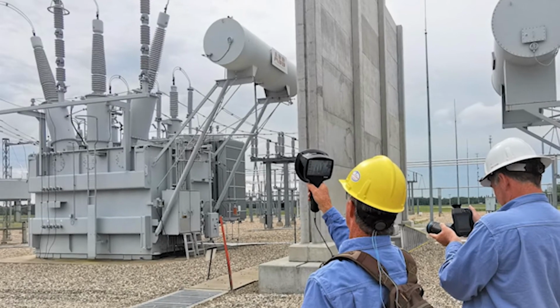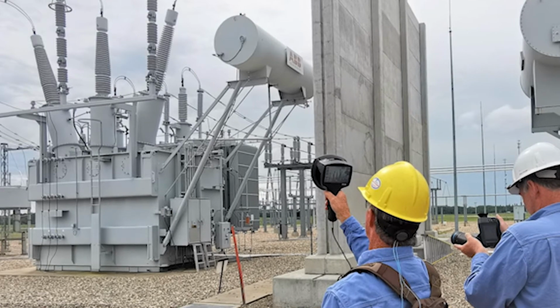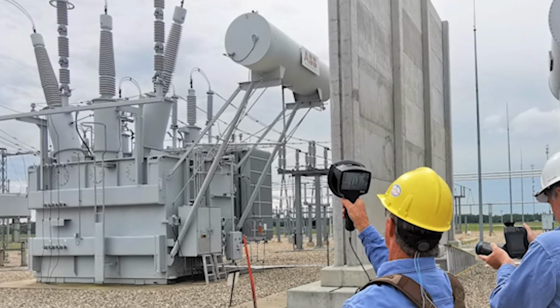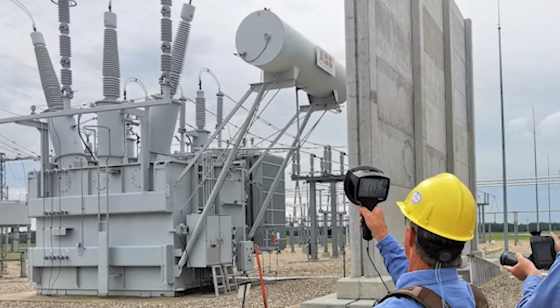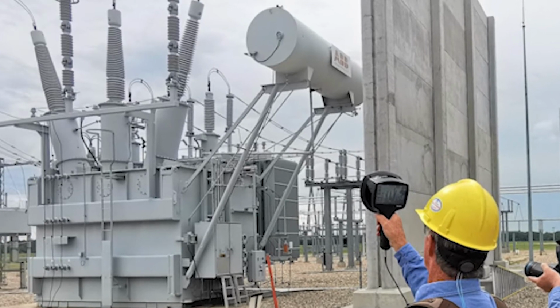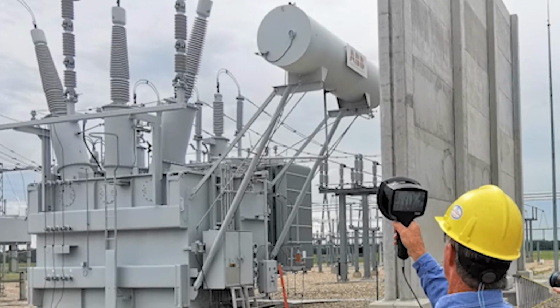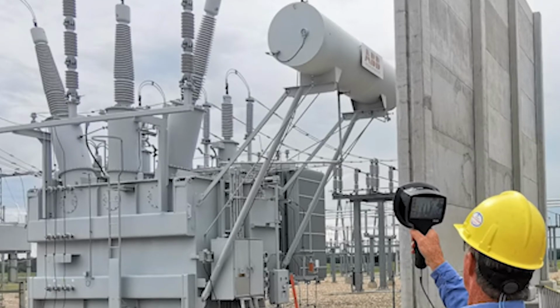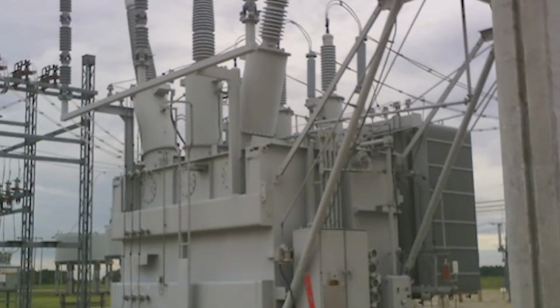Rick has a good clear view of the transformer. He is looking for corona hotspots, and he is taking a good look up and down the cooling fins, the primary bushings, the secondary bushings, and the conservator tank. Elton is looking through the GS77 to see if there's anything infrared that stands out. This image is what the GS77 sees in full spectrum. This is a snapshot used for documentation. We are looking for obvious signs of discoloration and any other contaminants on the vessel from animals or insects.